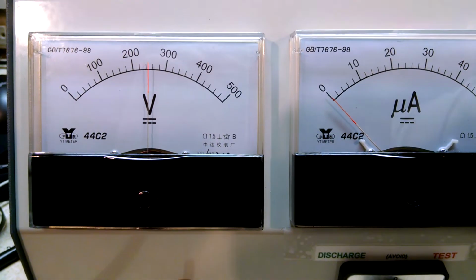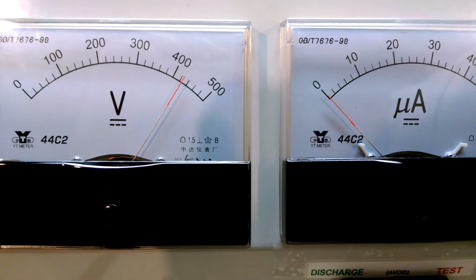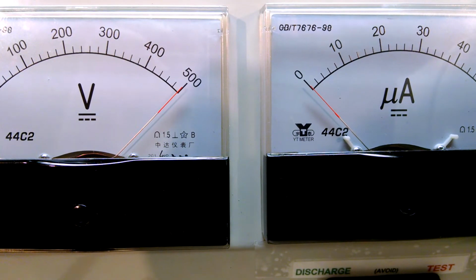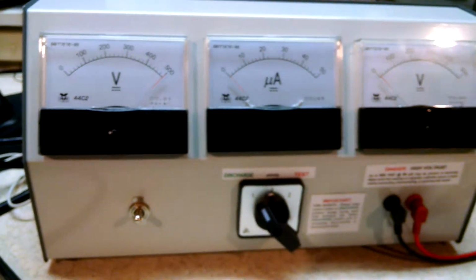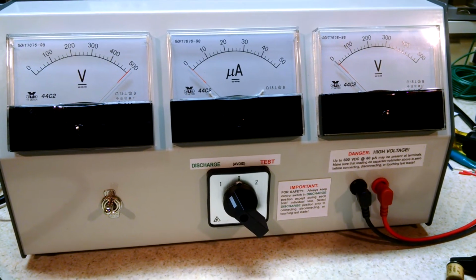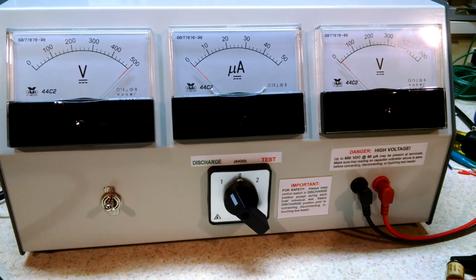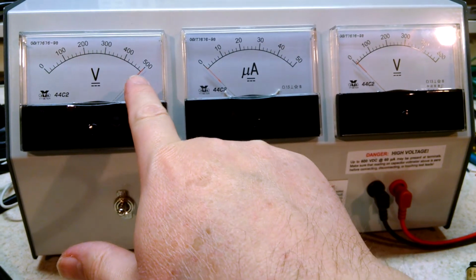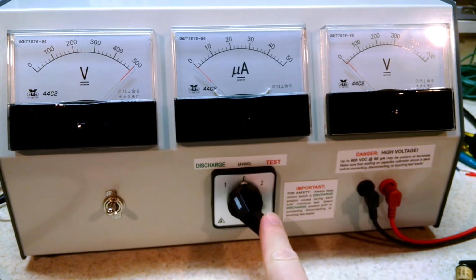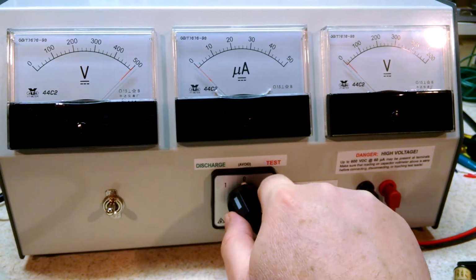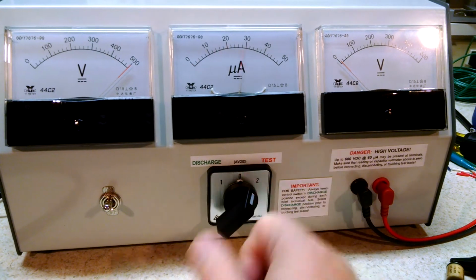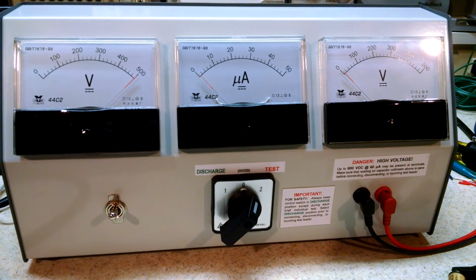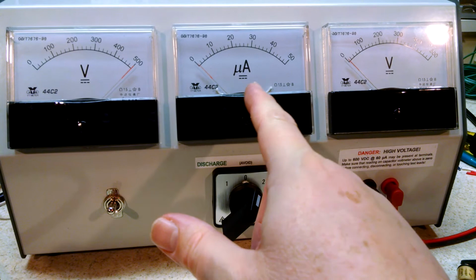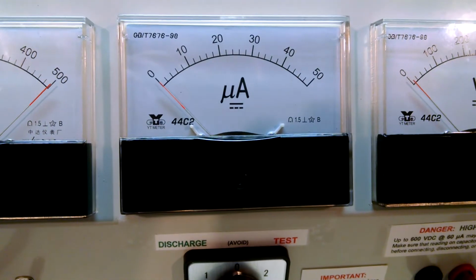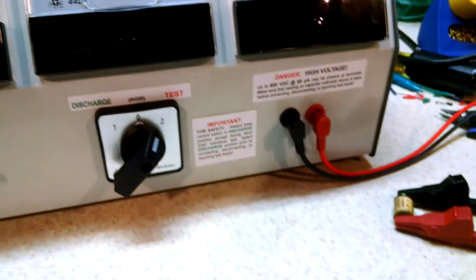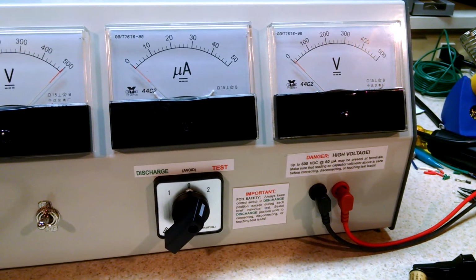Let's take the voltage up all the way here. Alright, there we are. We're resuming with this capacitor, the good capacitor. We're now at 500 volts DC. We're going to throw the test switch and see how much leakage it has. And there we can see that it zoomed up, charged, and now it's back down to basically 0 there. So there, ladies and gentlemen, that is a good capacitor.